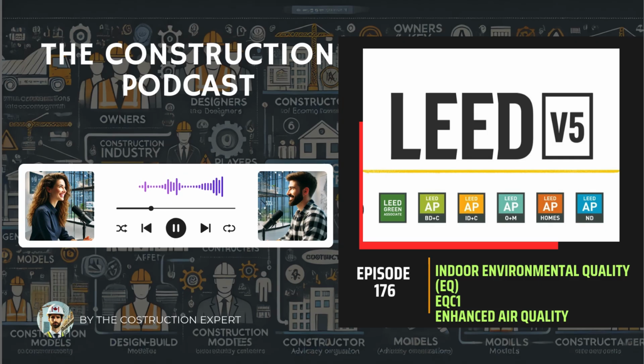You've hit on precisely the core control challenge with option 1 in VAV systems. It's a major hurdle. The system must be designed and controlled to decouple the thermal control, maintaining temperature, from the minimum ventilation requirement. Decouple thermal from ventilation. Exactly. The VAV system's control sequence has to be programmed very carefully, so that when a space is thermally satisfied, meaning the temperature is stable, the thermostat isn't calling for cooling, and the VAV box damper starts to close down to reduce total airflow, the system still ensures that the minimum required outdoor air ventilation for that space, the amount needed for breathing based on occupancy, plus the 15% or 30% enhancement, is maintained.